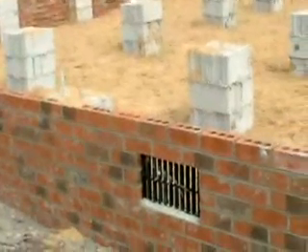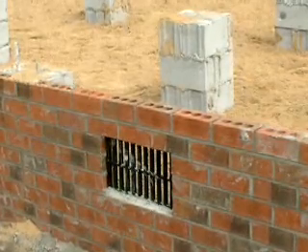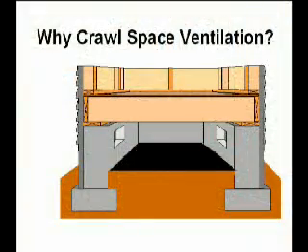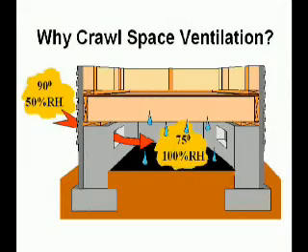In wall-vented crawlspaces, foundation vents are installed to passively vent excess moisture to outdoors. This passive drying effect comes into question during the summer, when warm and humid outdoor air enters the crawlspace through the vents and adds moisture instead of removing moisture.